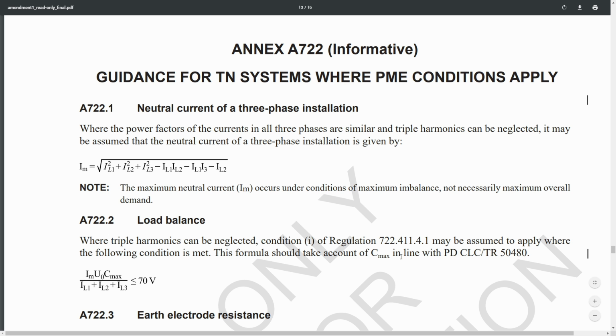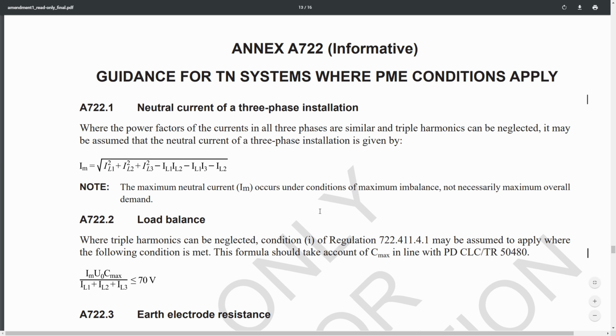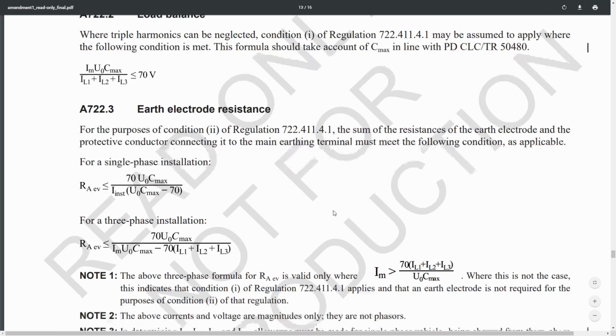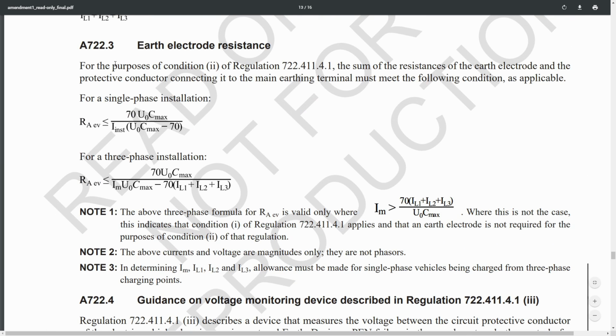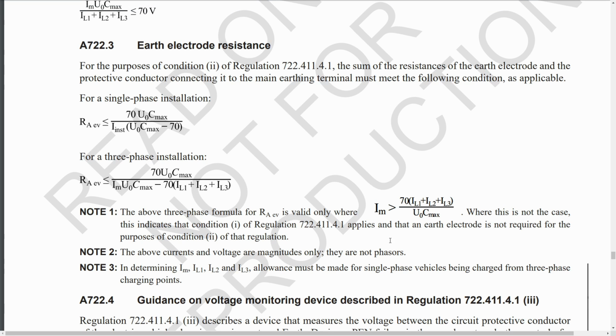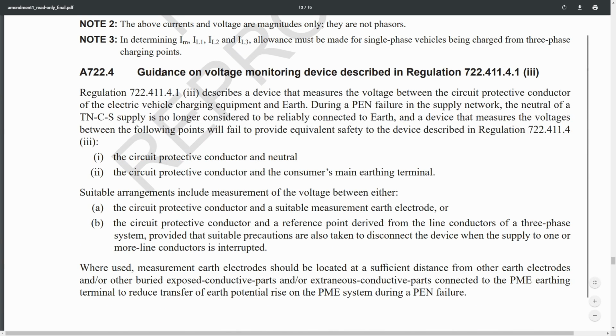It's just, again, some minor adjustments to some of the items within here. This is just guidance for TN systems where PME conditions apply. Calculating the neutral current of a 3-phase installation, load balance, earth electrode resistance, and so on. And of course, you can do all these calculations if you want to, but if you do this calculation here, you're looking for an earth electrode. That's where you're connecting it to the PME terminal and having your electrode as well. It comes out in the region of sort of 2 or 3 ohms or something in most cases, which I say is incredibly low. So, bit of an adjustment here.